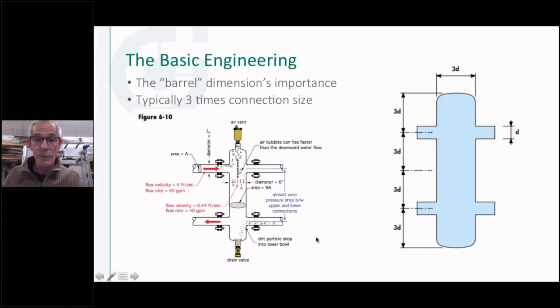So there it is. If you want to weld up one out of some pipe, if you want to make one out of copper and T-drill the side of it, whatever you want to do, there's the magic number. Now there is a little bit of engineering formula that we use, and at some point when you get into 12 and 14-inch pipe sizes, that math, we calculate it because you don't always find a pipe size exactly what you need. So we can kind of go between the lines a little bit. There is some math involved in sizing it exactly right, but the basic rule of thumb is a 3-to-1 relationship will assure that you've got plenty of space to make that separation work.